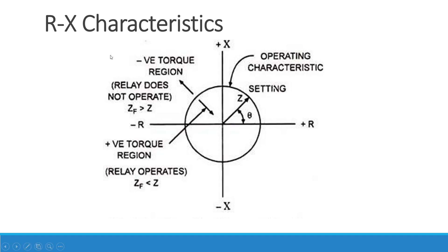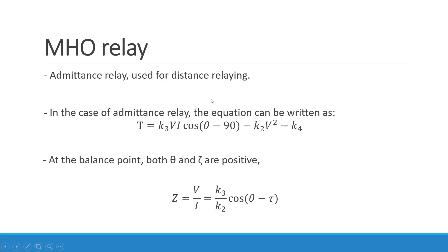From these characteristics you can observe that distance relays are inherently non-directional — the relay will operate for both forward and reverse directions. In order to overcome this, a different type of relay called the Mho relay has been developed. There is also another solution which involves using a directional element in series with the distance element.